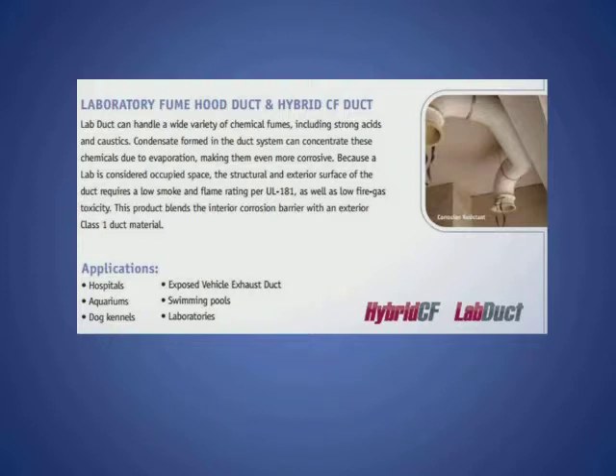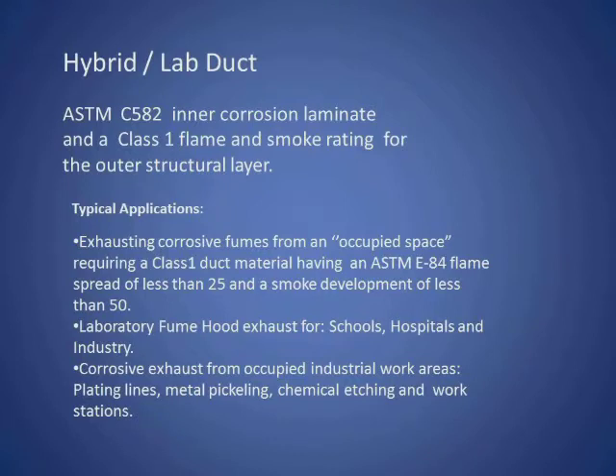Again, applications are hospitals, aquariums, dog kennels, exposed vehicle exhaust, swimming pools, laboratories. The hybrid lab duct, principally, the interior follows ASTM C582, and that defines what the inner corrosion barrier is: the corrosion-resistant resin and the C-veil or another veil, depending on the chemical application. And the exterior would have the flame and smoke rating required for the exterior and that structural layer.